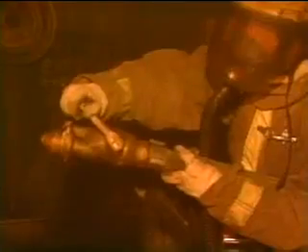As you enter the room, aim the nozzle toward the overhead, where the heat and smoke are. Use a straight stream pattern in 1 or 2 short blasts. The water immediately absorbs great amounts of heat, producing steam, which in turn smothers most or all of the flames. When flames can no longer be seen, straight, short bursts of water can be used to extinguish any remaining or smoldering fire. Once all visible fire is out, move in and overhaul the area.